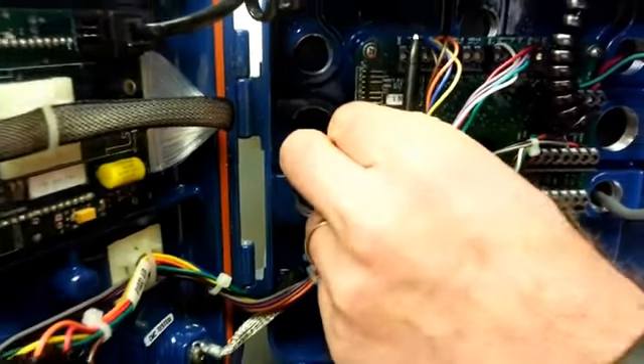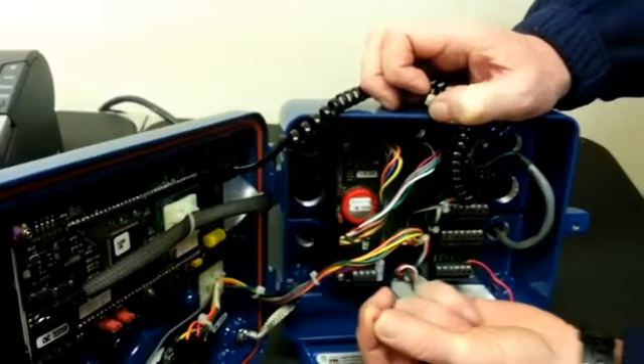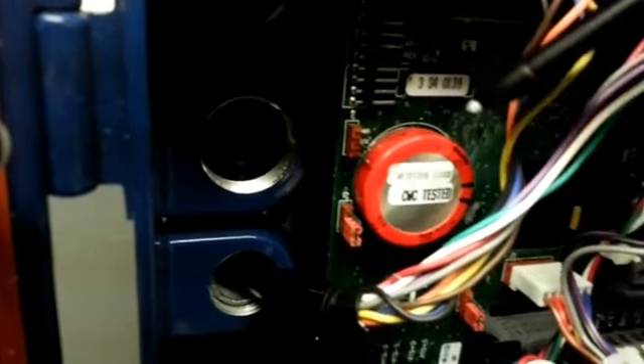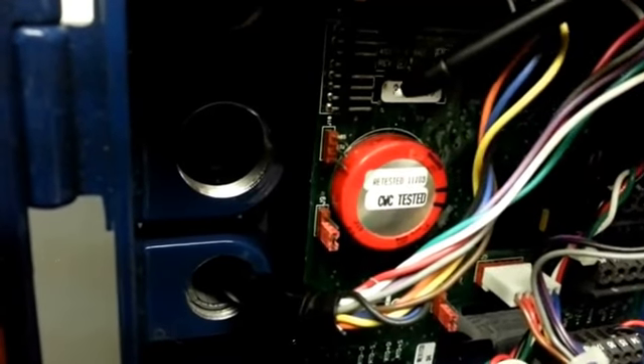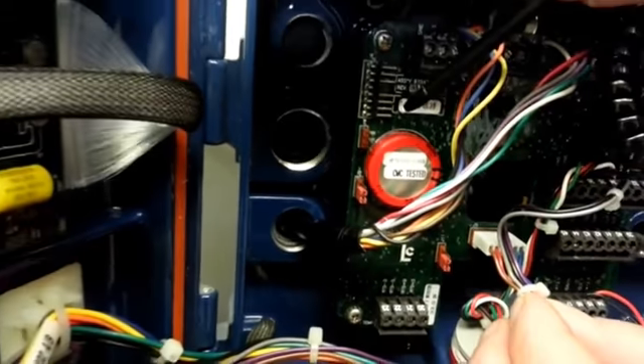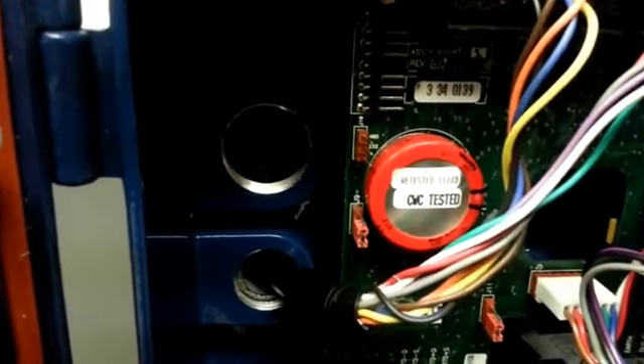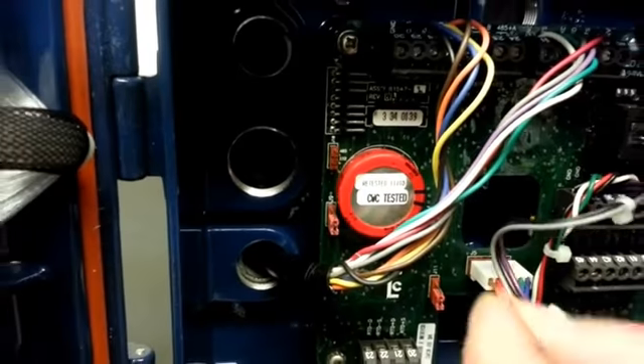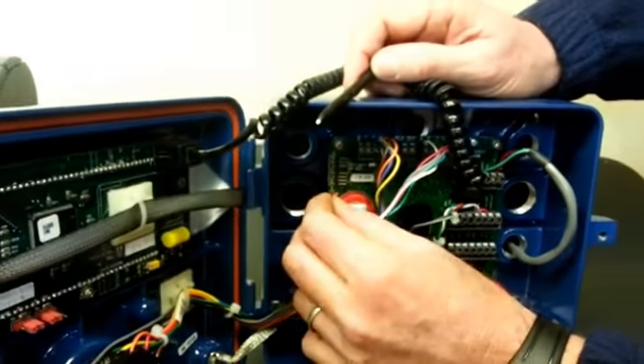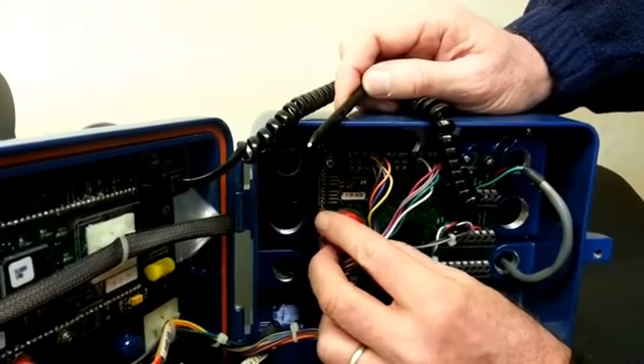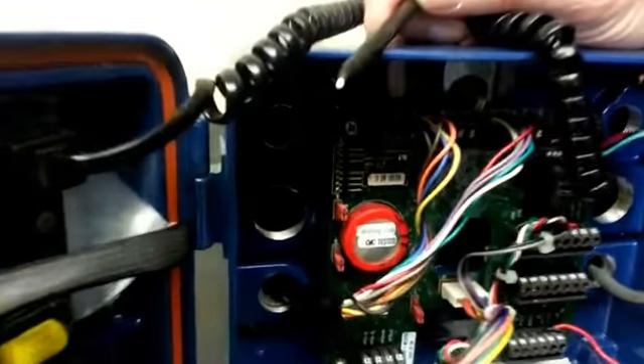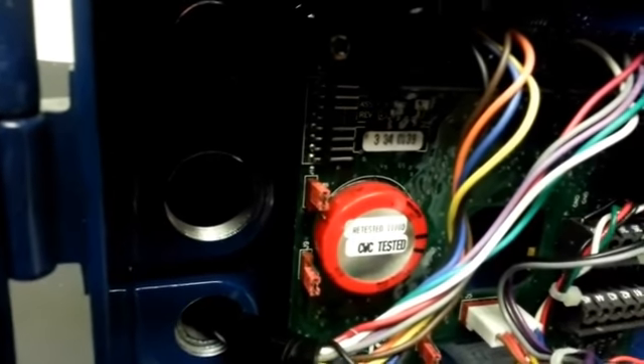Make sure it's powered off. That jumper can be pulled out, and you'll notice there are 3 pins. The J10 jumper is either going to be in the 232 position or the 485 position. For Digital Dispatcher, it needs to be in the 485 position. The other most common board is labeled A and B: A is for 232, B is for 485. On this board, to get it in the 485 position, we capture the 2 top pins, and that's done. Now it's prepared in the 485 position and ready for Digital Dispatcher.